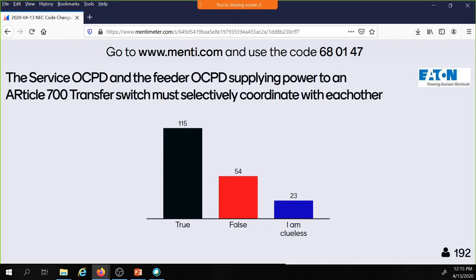The service overcurrent protective device and the feeder overcurrent protective device supplying power to an Article 700 transfer switch must selectively coordinate with each other. We got 115 trues, 54 falses, and 23 I am cluelesses. If you're going by the NEC, I didn't say per the NEC. I should have, because some of those 115 may be. This is a good design goal. It's not necessarily a code requirement.